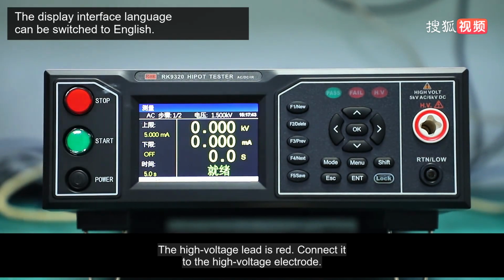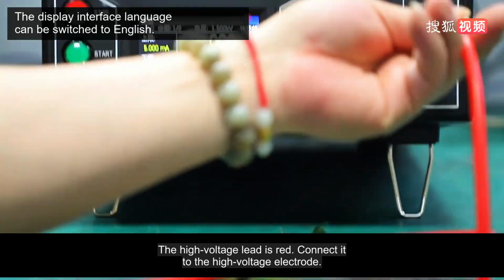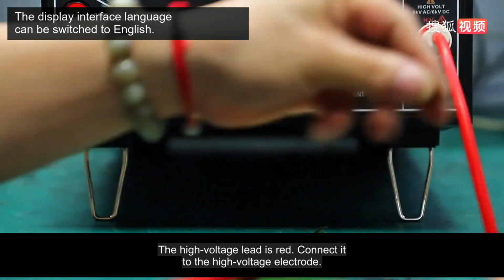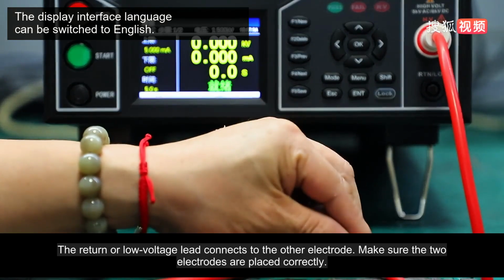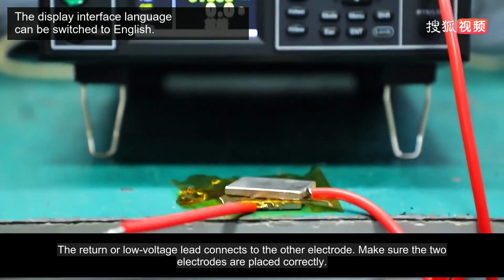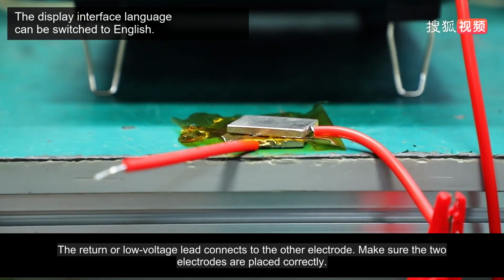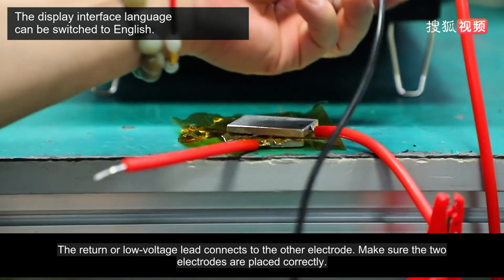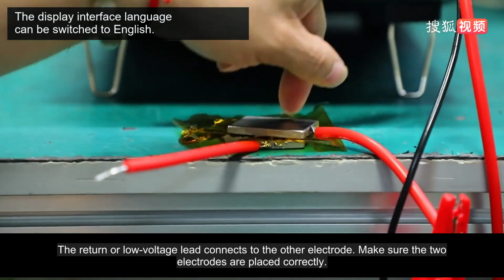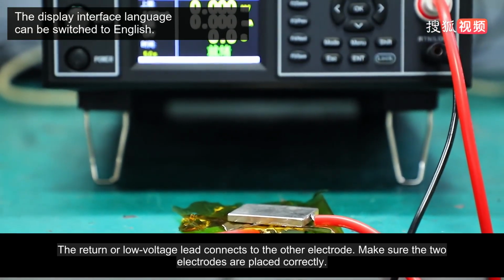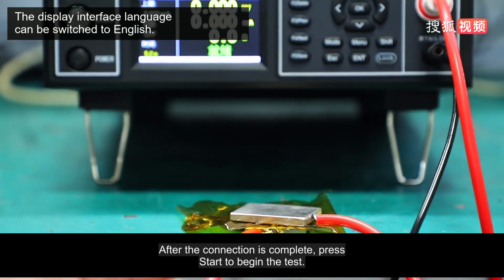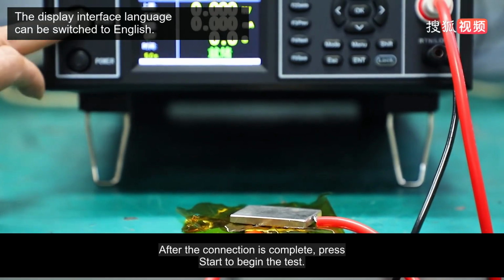The high voltage lead is red. Connect it to the high voltage electrode. The return or low voltage lead connects to the other electrode. Make sure the two electrodes are placed correctly. After the connection is complete, press Start to begin the test.